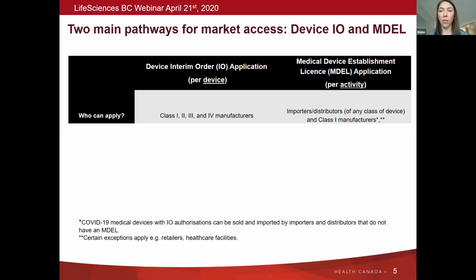Class 1 medical device manufacturers have the luxury of choosing between the interim order authorization pathway and the establishment license authorization pathway. I will walk you through some of the differences between the two, which will hopefully help you pick the pathway best suited to your needs. As I mentioned, the device interim order authorization is for all classes of medical devices, and it's specifically for manufacturers. The manufacturer is the person ultimately responsible for the device. It doesn't have to be the factory or the person managing the factory that does the physical fabrication. It's the person whose name and address goes on the labeling at the end of the day, and who is responsible for complaint handling, recalls, all that fun stuff.